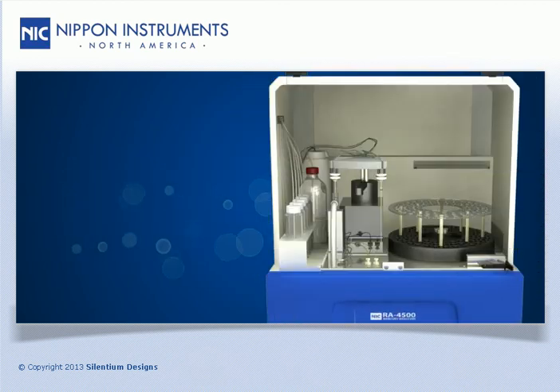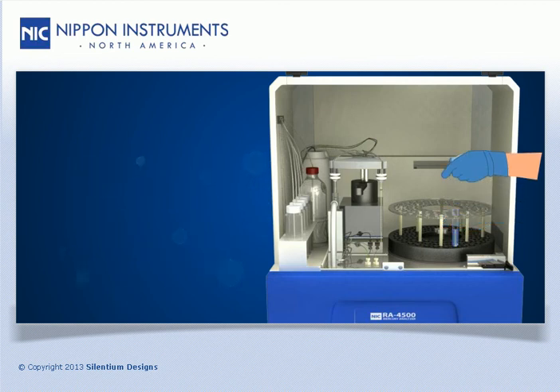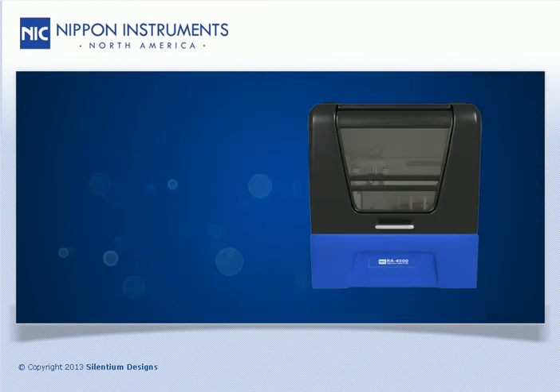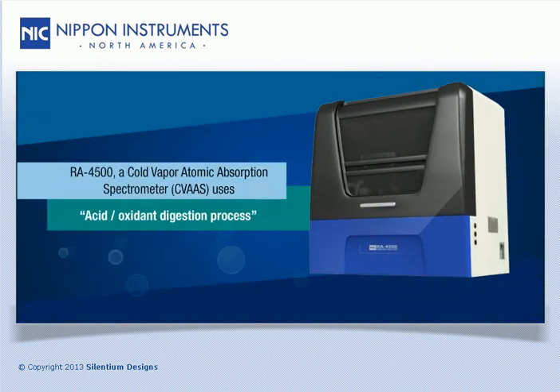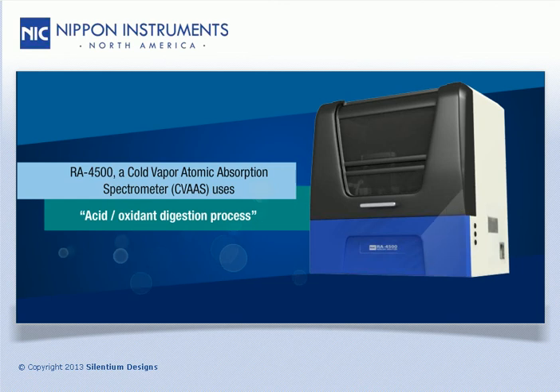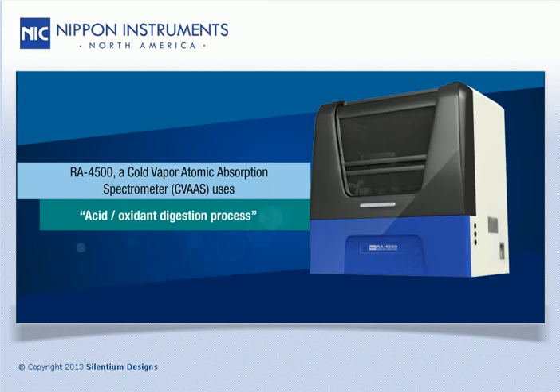With the RA4500, all you have to do is simply load your sample and the RA4500 does the rest. Using an acidic oxidation digestion process, it converts all forms of mercury in the samples to the oxidized and water-soluble inorganic species, which is then analyzed by cold vapor atomic absorption spectrometer.